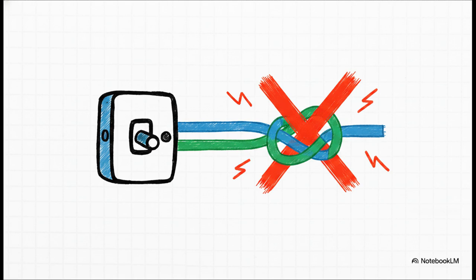After the power passes through the RCD, the neutral and PE lines must never connect again. If you cross them, you're creating those illegal multiple bonds we talked about. This allows normal return current to leak straight into the earth, which completely bypasses the RCD's delicate leak sensor. The result? Well, best case, your system suffers from constant frustrating nuisance tripping. Worst case, it totally fails to protect you when a real dangerous leak occurs.